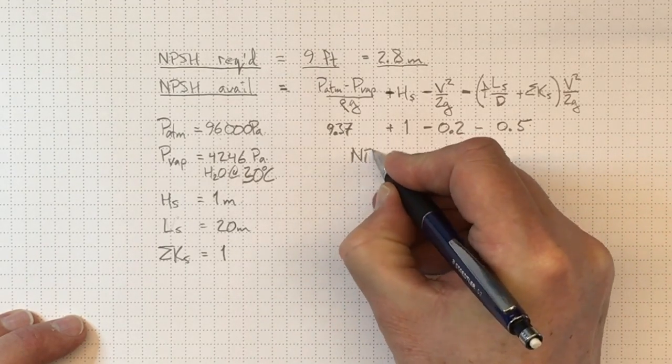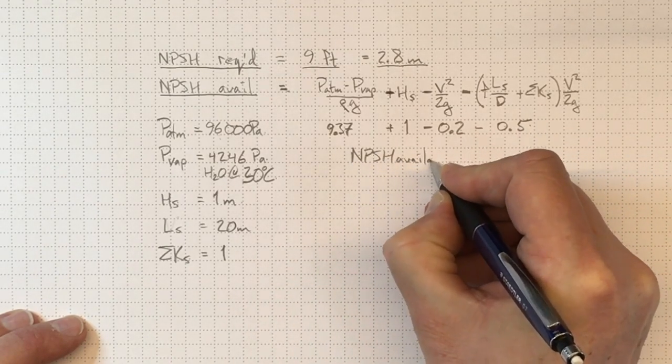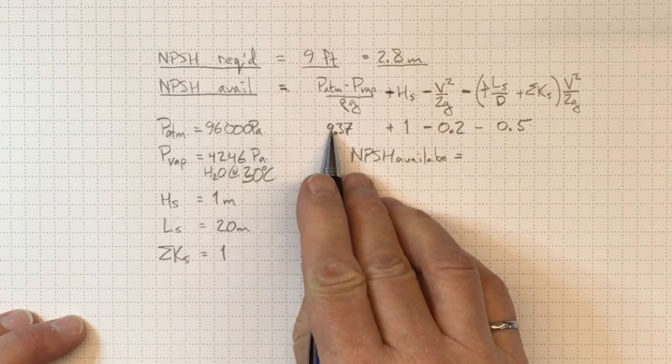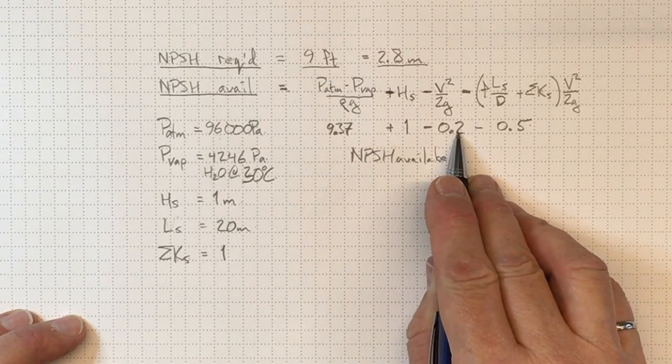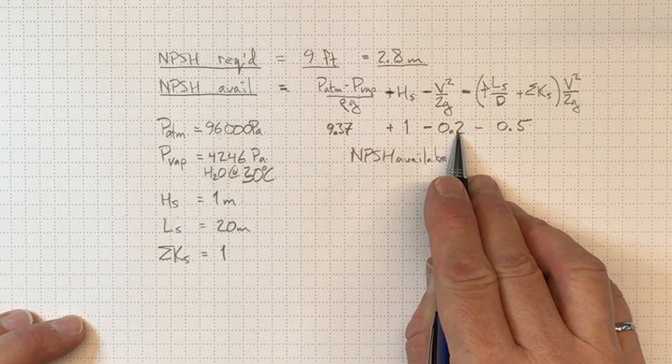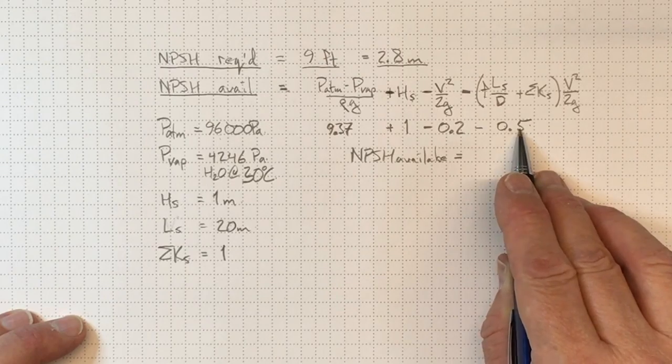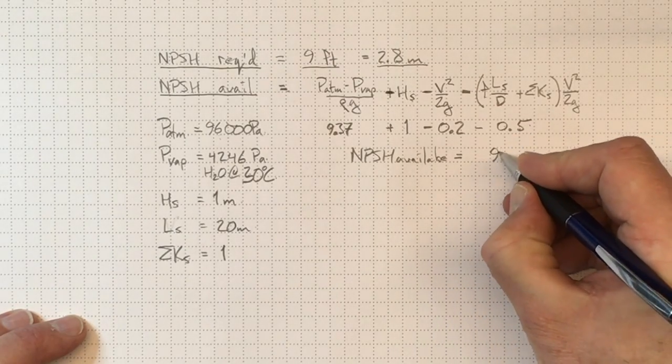And we'll wind up with a net NPSH available equal to 9.37, 10.37, minus 0.2 takes us down to 10.17, minus 0.5 takes us down to 9.67 meters.